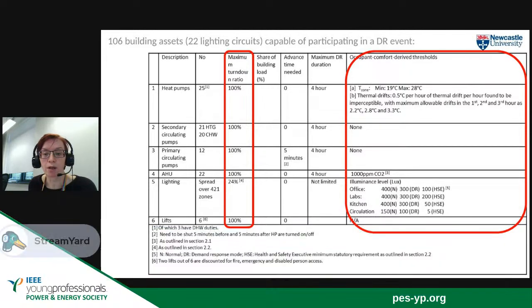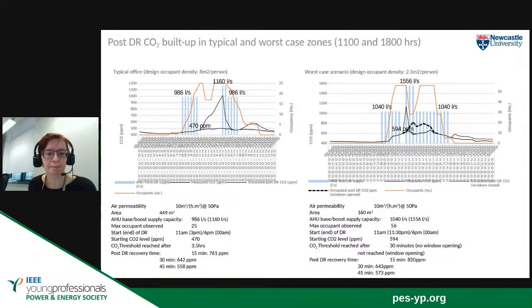So great, we did all this audit, we looked at the building, we looked at all these loads, and we identified what we could turn down. So this is what it looks like when you do a turn down event for the air handling unit. We've got a typical office and then a worst case office. So the left hand side is typical and the right hand side is worst case in terms of carbon dioxide levels that we achieved in that space.